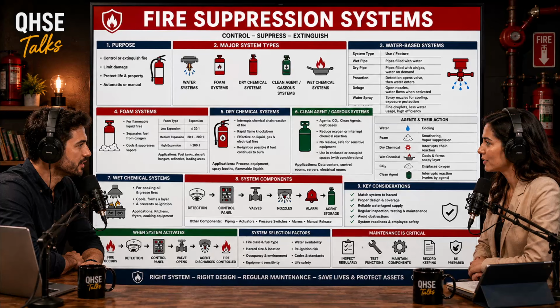Yes, it's a nightmare. Therefore, for Class B, you cannot rely on cooling with water. You need to inhibit the release of combustible vapors or reduce the oxygen concentration using specialized foams or dry chemicals. Okay, moving on to Class C, energized electrical equipment. The operative word there being energized. Right, because the hazard profile here isn't just the fire, it's the electricity. Class C fires require strictly non-conductive extinguishing agents. Precisely.